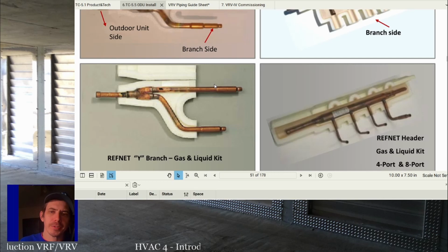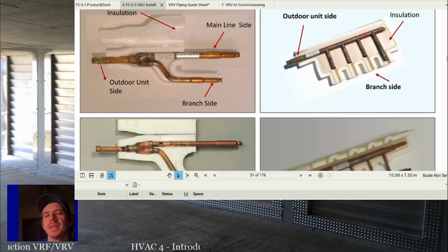Another tangent we can go on real quick is that they tried VRF style units as early as I know of in the 80s, and I think it was York that was trying to serve multiple indoor units off of a single outdoor unit. Where that tends to get complicated is getting the refrigerant to split evenly as necessary to serve the multiple units. My understanding, and this is all secondhand knowledge, is that York basically just used regular plumbing tees to separate the refrigerant, and it just didn't work very well. Whether it was their piping rules or the actual tees they used, they just didn't work right.